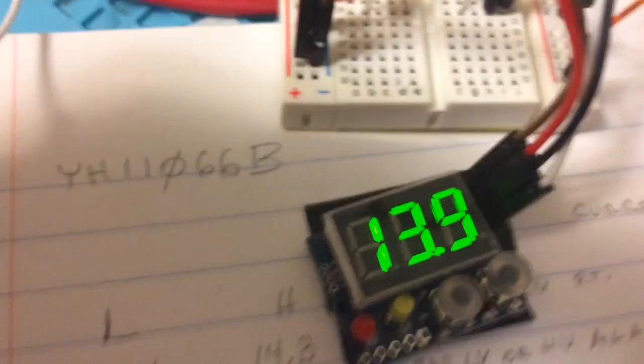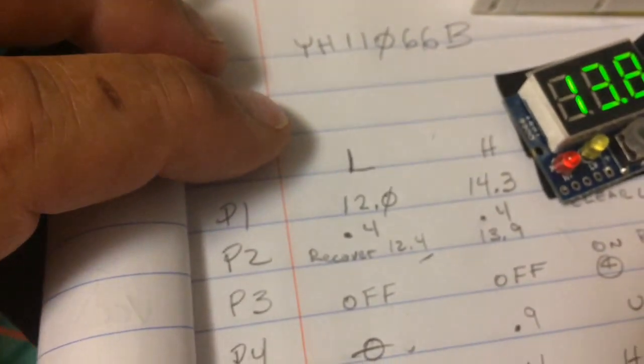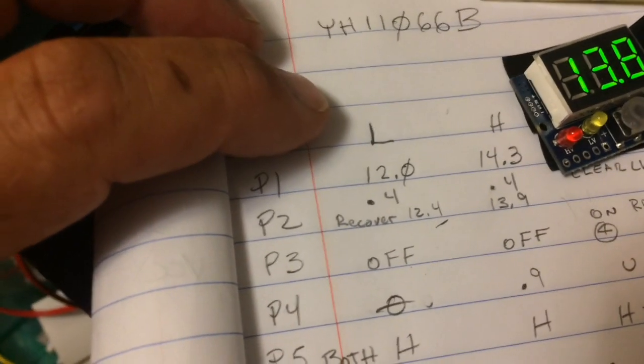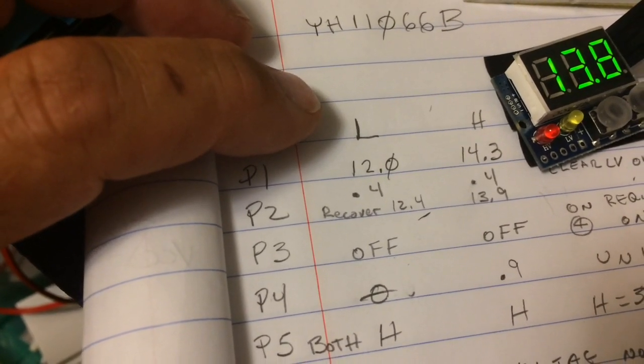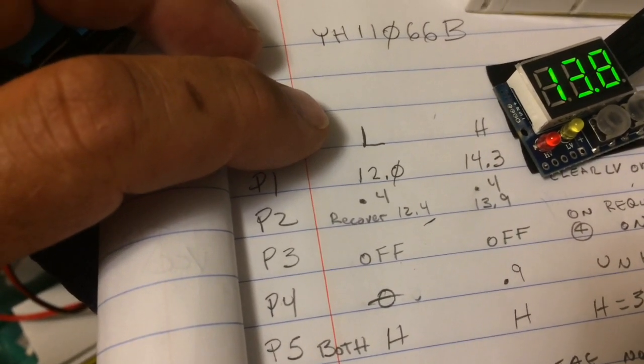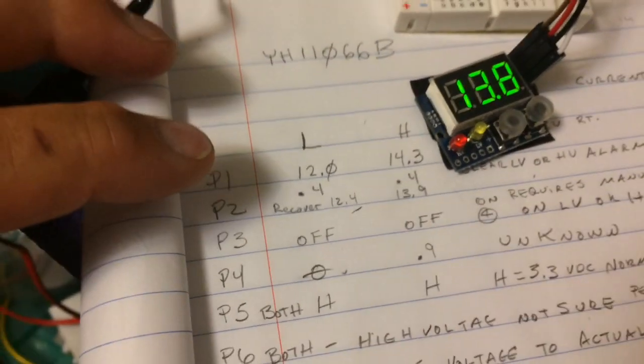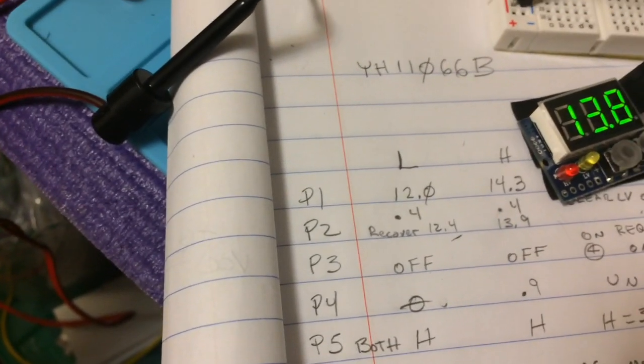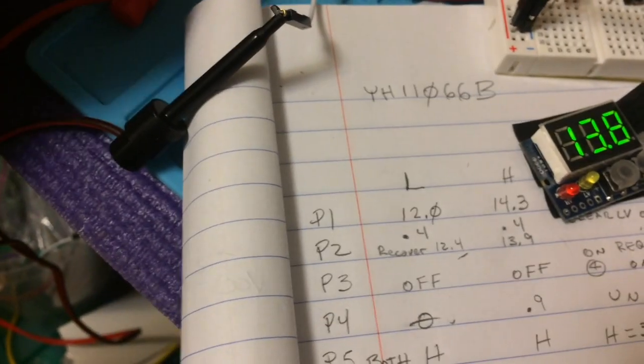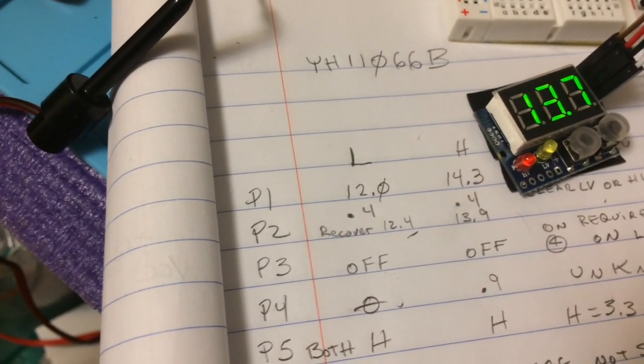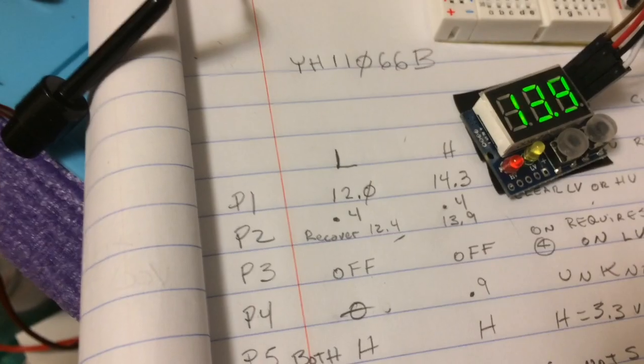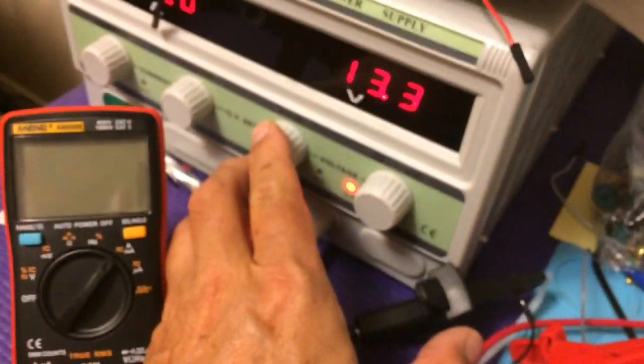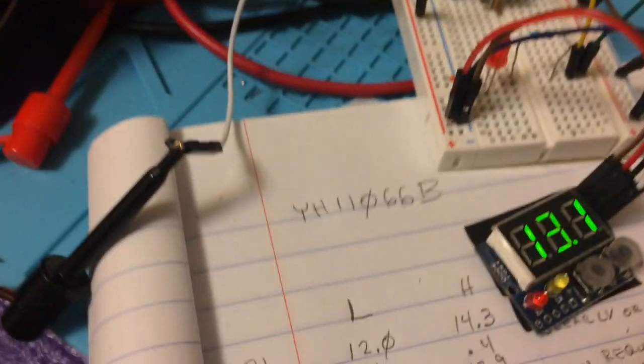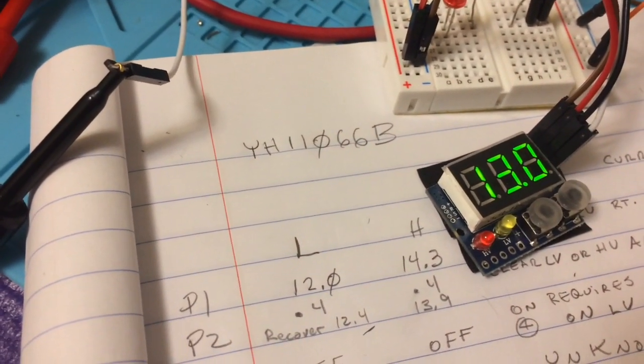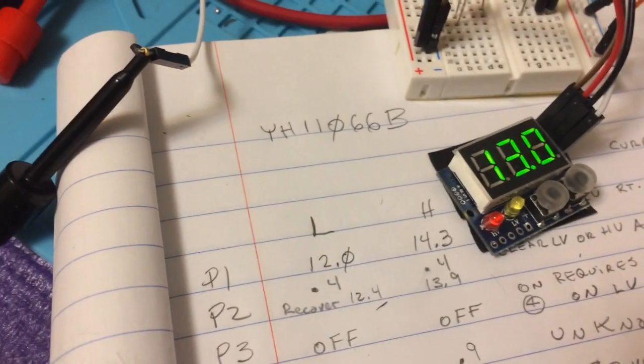Now I'm going to go over this. Right now I've pre-programmed these values where it's 12.0 low and 14.3 high. I'm going to go down - I've got a variable power supply here that I'm running. It should hit the low voltage alarm at 12.0.